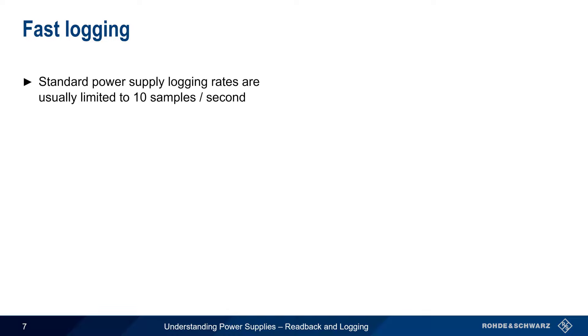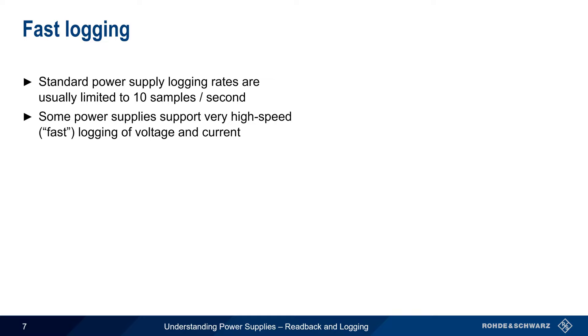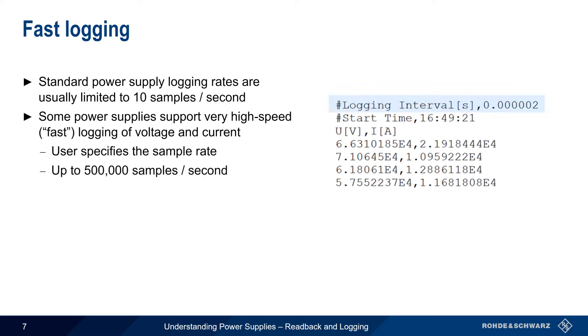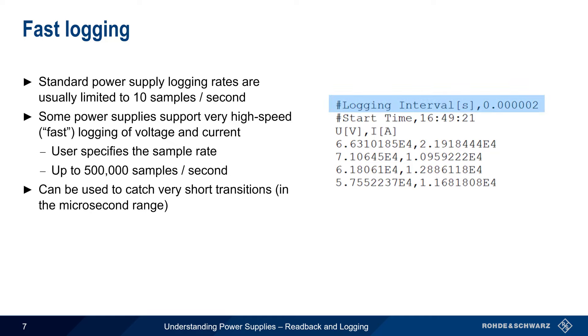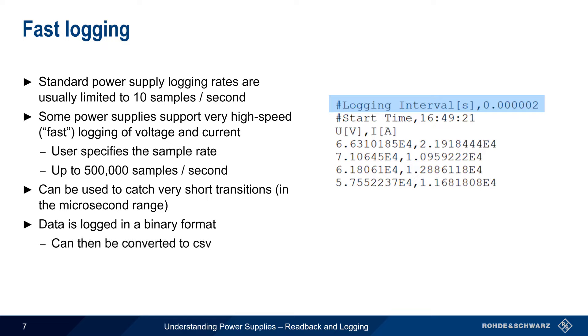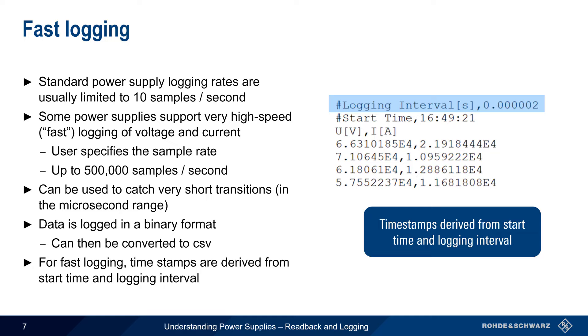The standard logging rate in most benchtop power supplies is usually limited to 10 samples per second. Although this is sufficient for many measurement tasks, it might not be fast enough to capture transients or other very short duration events. Therefore, some power supplies have a special high-speed or fast logging option. This mode allows the user to specify the sample rate of voltage and current, which can be up to 500,000 samples per second, meaning fast logging can capture transitions that occur in the microsecond range. Fast log data is stored in a binary rather than text format, and a utility can then be used to convert this binary file into standard CSV format. Note that a fast log file doesn't explicitly contain timestamps, but timestamps can be easily derived from the start time and logging interval.